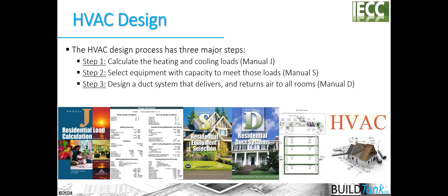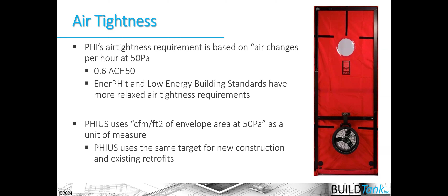Air tightness: they use different metrics. One is air changes per hour, the other is CFM per square foot of envelope area. An analogy that makes sense to me for why CFM per square foot of building envelope is better: you wouldn't estimate the gallons of paint you need for your wall system by measuring the volume of the house. It's the same with air leakage - it's all about the surface area of the building and how many holes are in it. So I prefer the CFM per square foot of envelope area metric over the ACH metric.